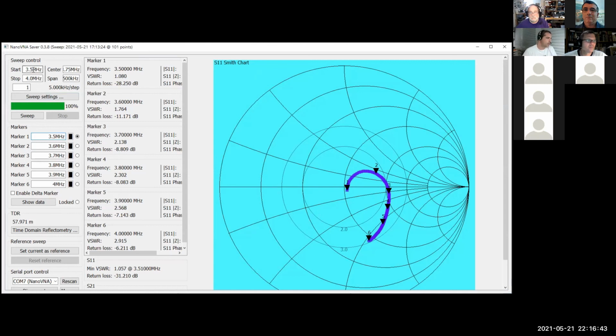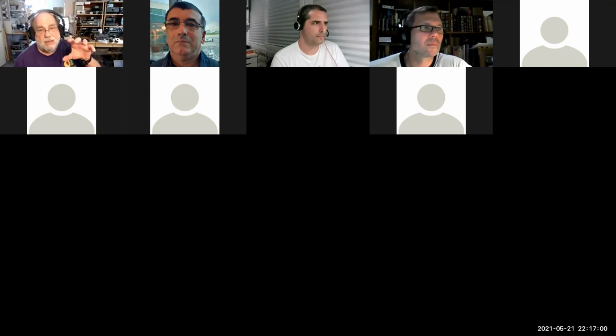So if you wanted to adjust it for 2 meters or 70 centimeters, then you calibrate it immediately before the test, or you calibrate it beforehand and save it. Cover those calibration files. When you first turn on the NanoVNA, if you're on battery power, it defaults to, I think it's called calibration 0. I call it 1, but you know, engineers call it 0. So that's the default when you first turn it on. But then I can go with a little mouse into the NanoVNA, reading the little print, and I can pick calibration file 1 or 3 or 5. On the one I have, you can only save 5.